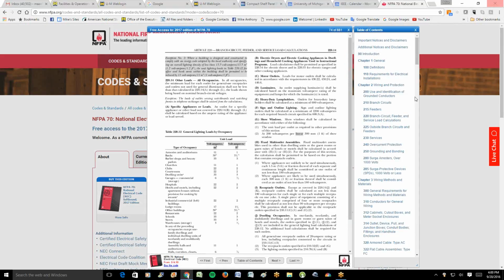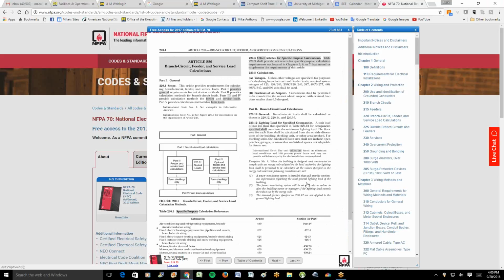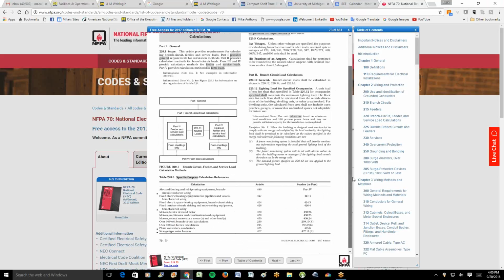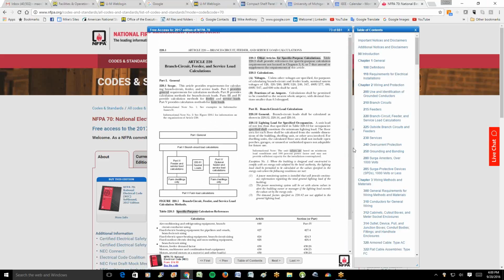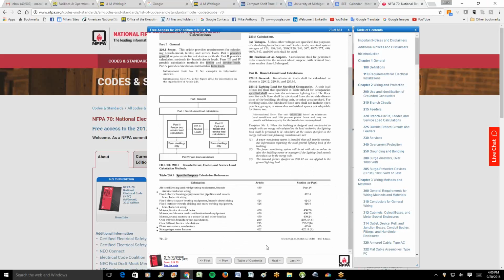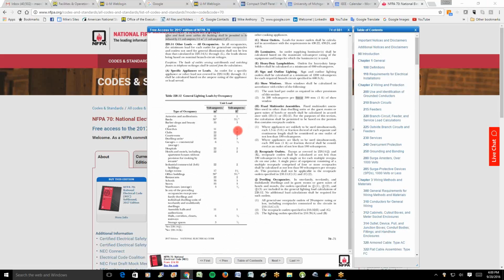And so the table that she's talking about is right here. This is the exception that we got in last time, and this is important because it is determining the size of your power system. I think Jim was talking about the expansion of the lab. Now we all came to understand that the lab itself was a different type of occupancy. But for most buildings in higher education, we're using this table for lighting loads, and we're finding ASHRAE is limiting us to 0.9 watts a square foot while NEC is making us design for 3 watts a square foot. Something's wrong with this. I think I'm preaching to the converted here.